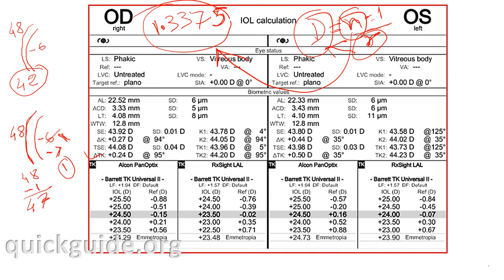Some machines have different keratometry indices, but IOL Master has always used 1.3375 since it was first introduced. You can still use the same keratometry index for IOL Master 700, which means you do not need to change your A-constants for IOL power calculation. So basically, TK is not net corneal power — not anterior minus posterior — but it adjusts for deviations in posterior corneal power from average values and reconciles them with anterior corneal values, so you can use it in any formula. If you have questions, log on to quickguide.org and I will be happy to answer.